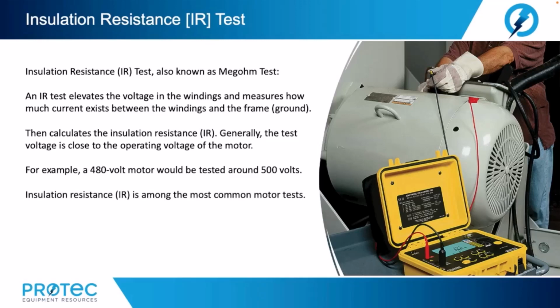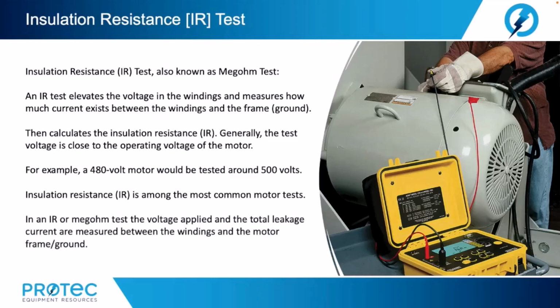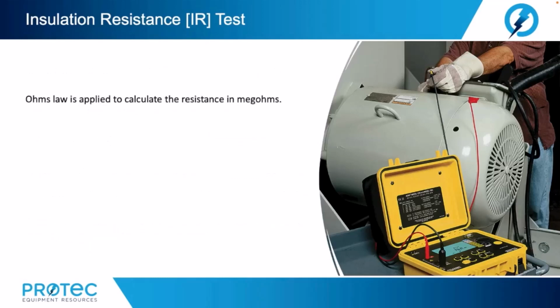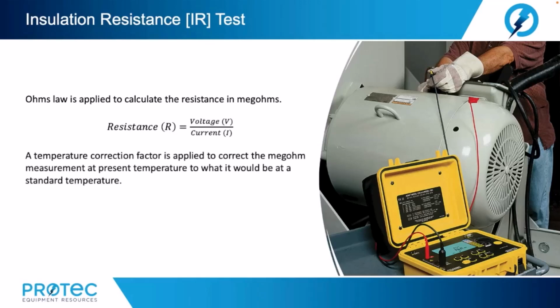Insulation resistance is among the most common motor tests. In an insulation resistance or megohm test, the voltage applied and the total leakage current are measured between the windings and the motor frame or ground. Ohm's law is applied to calculate the resistance in megohms. Basically, resistance equals the voltage divided by the current. A temperature correction factor is applied to correct the megohm measurement at present temperature to what it would be at a standard temperature. Now, according to IEEE 43 and ANSI/EASA standards, the standard temperature is 40 degrees C.